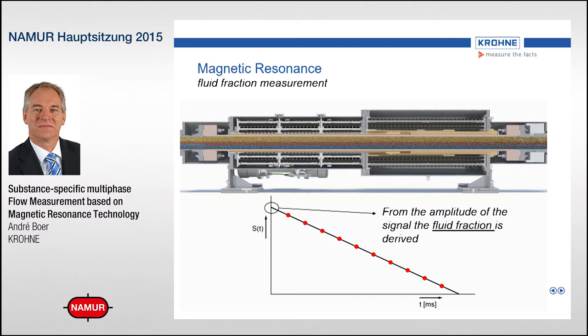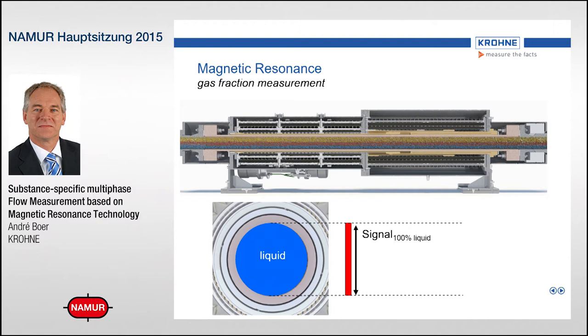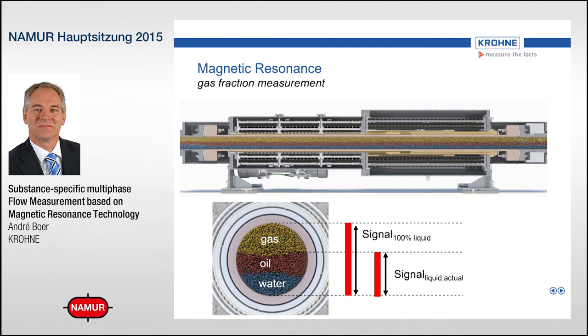It's not just the time it takes for tagged protons to flow out of the measurement section that we need — we also need the initial amplitude. When we tag a certain volume of protons, we look at the amplitude of the received signals. This amplitude is a measure of the fluid fraction. When the complete cross section is filled with liquid, we know what the signal would have been, as liquids give a very strong signal back. Part of the cross section was filled with liquid — the mixture of oil and water — and the rest was gas. So the missing amplitude corresponds to the gas fraction.